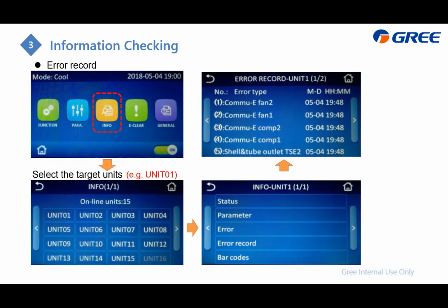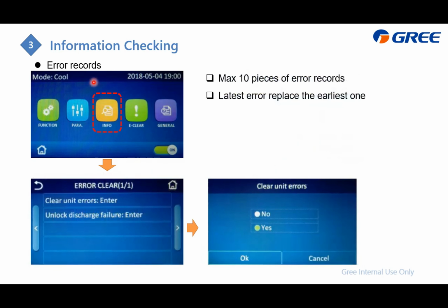Error recall. This one is similar: first select which chiller, and then press the error recall. It will display all the historical errors, including the error information, and also when the error happened. At maximum, we can store only 10 errors, which means the latest error will replace the earliest one. On the other hand, you can also manually clear all the errors.